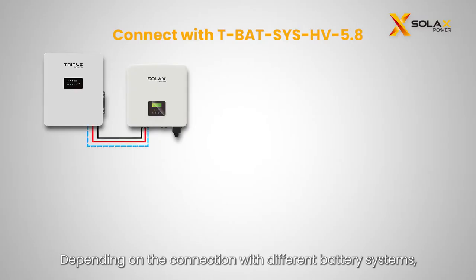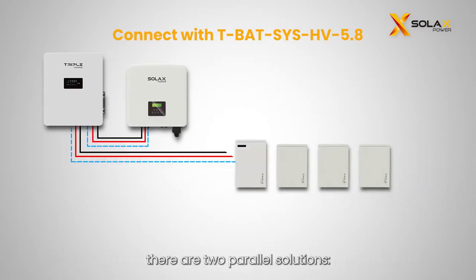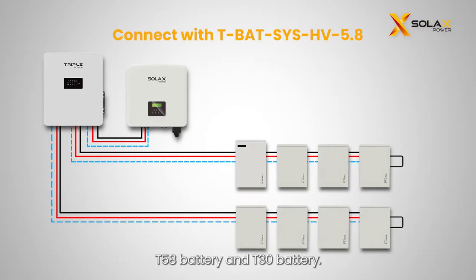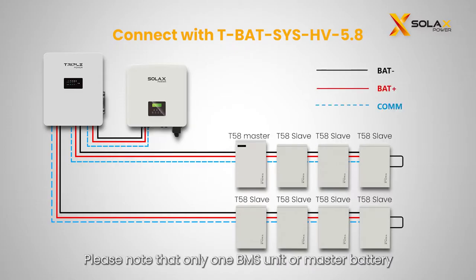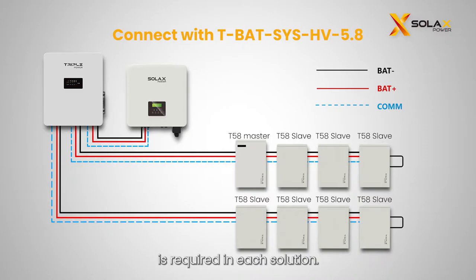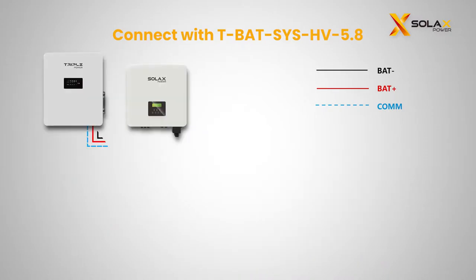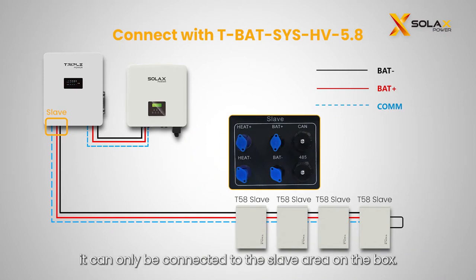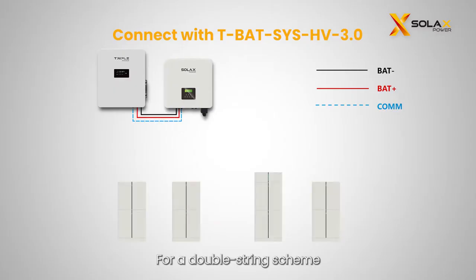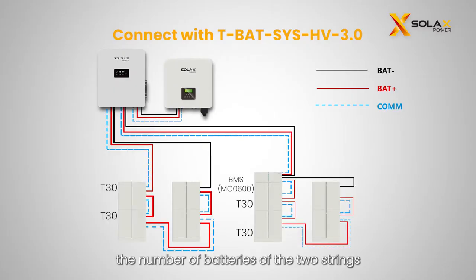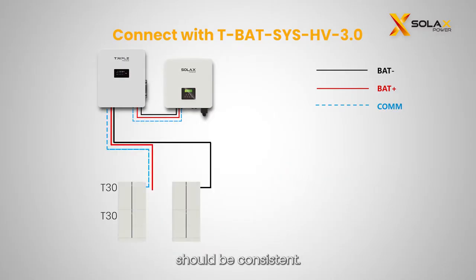Depending on the connection with different battery systems, there are two parallel solutions, T58 battery and T30 battery. Please note that only one BMS unit or master battery is required in each solution. When only one single string battery is connected to the box, it can only be connected to the slave area on the box. For a double string scheme, the number of batteries of the two strings should be consistent.